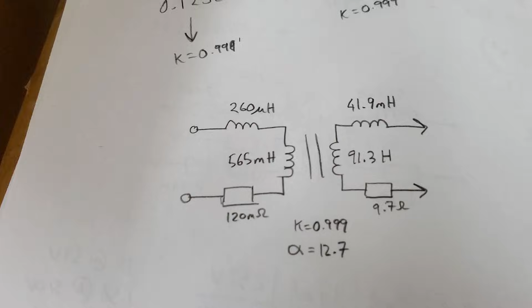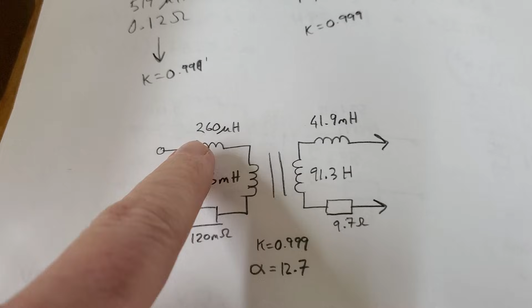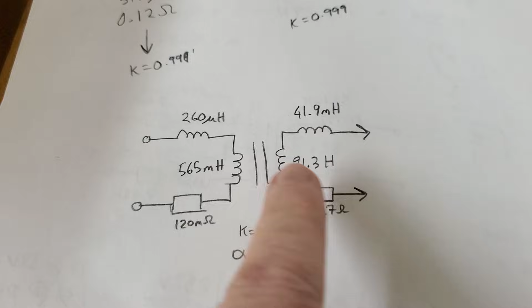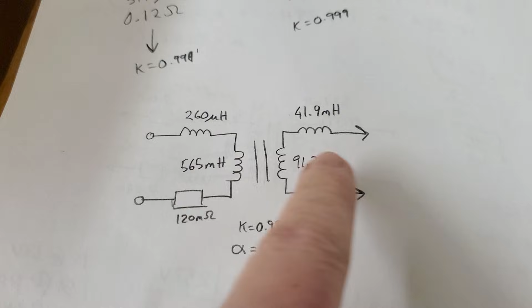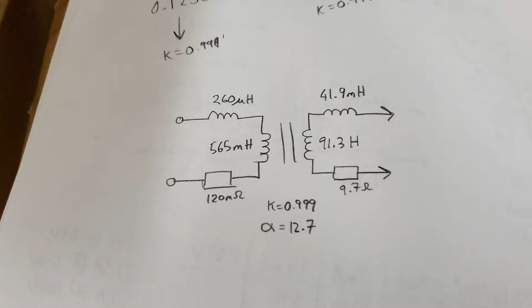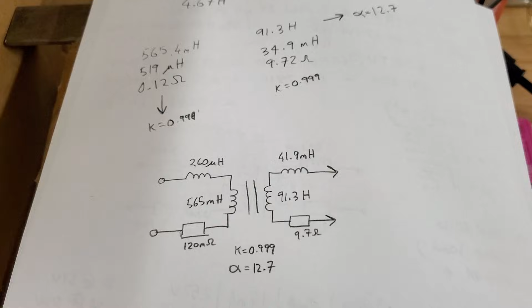So basically, this is what it would look like electrically. 120 milliohms series resistance. The leakage reactance on the primary is like 260 microhenries. You've got a transformer that's essentially 1-to-1 at that point, and 91.3 henries out and 41.9 millihenries leakage on the other side with about 9.7 ohms. So yay, math works. We analyzed the transformer, and it is consistent with what I understand of this transformer and what I measure by injecting a signal into one side. I get the turns ratio that is about 12.7.